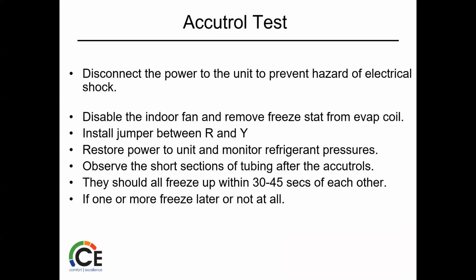So disconnect the power to the unit, right? Just because that's a safety thing. Disable the indoor fan. Take away that freeze stat from the evap coil. Again, depending on the unit, sometimes you don't have one. Jump out R and Y. Turn the power back on. Look at your refrigerant pressures. Watch that Accutrol manifold there. Obviously, they should all freeze up fairly evenly. If one or more doesn't, or not at all, then there's a problem there. So we're replacing that.